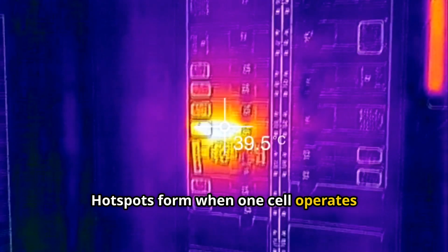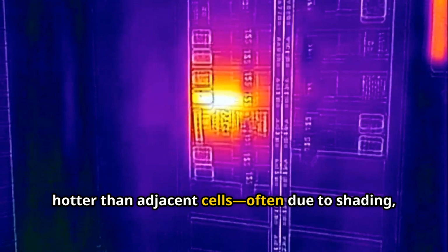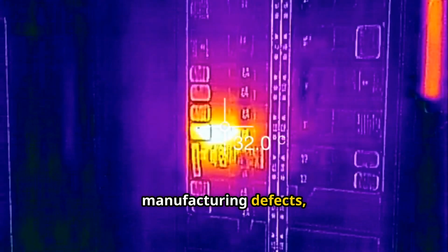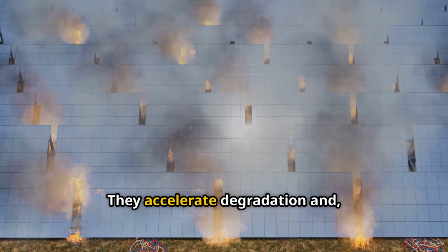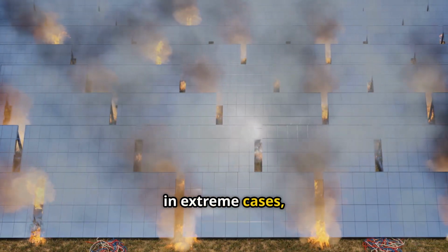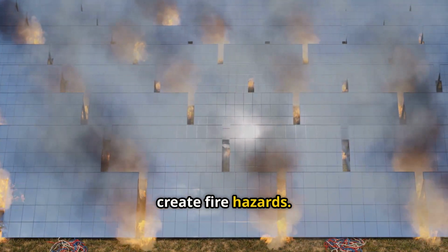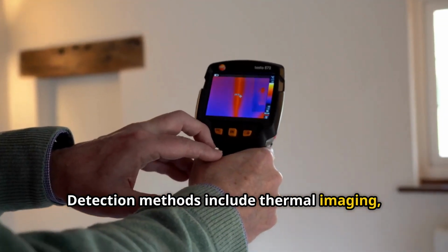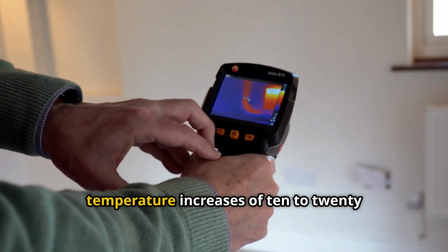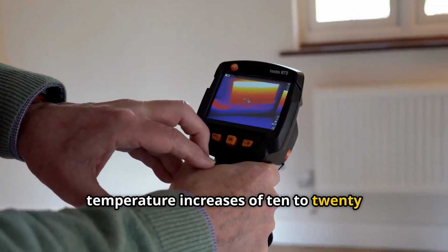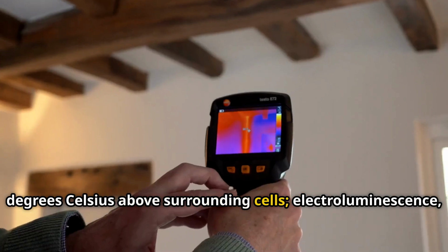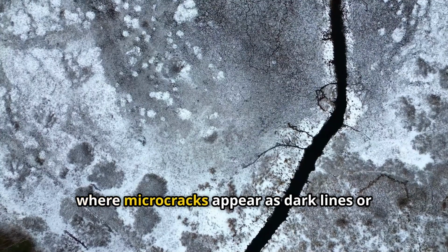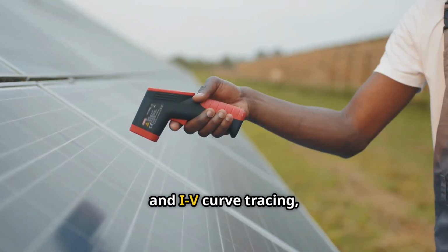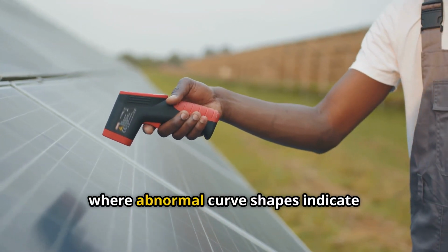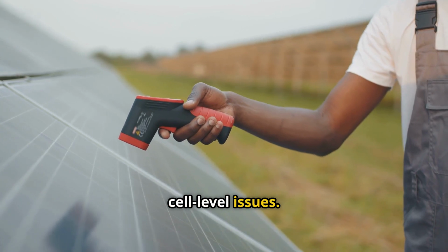Hotspots form when one cell operates hotter than adjacent cells, often due to shading, manufacturing defects, or prior damage. They accelerate degradation and, in extreme cases, create fire hazards. Detection methods include thermal imaging, where hotspots appear as localized temperature increases of 10 to 20 degrees Celsius above surrounding cells. Electroluminescence, where microcracks appear as dark lines or areas where current flow is interrupted. And IV curve tracing, where abnormal curve shapes indicate cell-level issues.